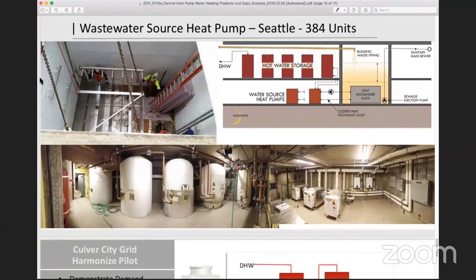It's easily explained in a p-h diagram, which is an enthalpy pressure diagram, but that usually gets over people's heads, so I won't go there. But in the refrigeration cycle, there's sort of a condensing side and an evaporator side, and the colder the water is, what it ends up doing is it positions you better on the next cycle, because now you're further along the chart, and so you get greater capacity, which leads to less energy use.